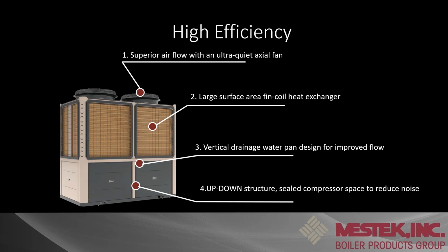So here is a breakout of it. It's high efficiency. Our fans on there are EC motors, so they're going to ramp up and ramp down based on the ambient temperature. We use an axial fan, which brings the airflow straight up the shaft and outside, and blows out the way the fan blades are rotating. On the larger surface area, the bigger the coil outside, the more transfer we can get. We know that with high efficiency boilers or even cast iron boilers, the more surface area we have, the more transfer we're going to have. That is why these coils are large, trying to gain as much transfer as you can.